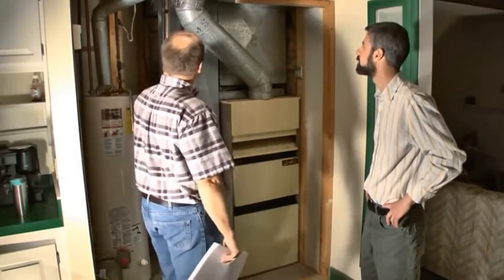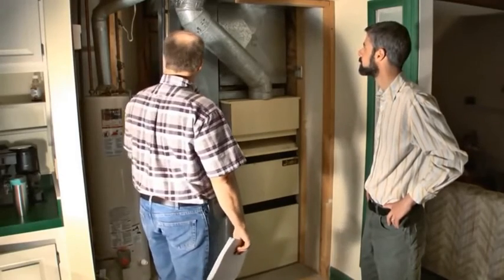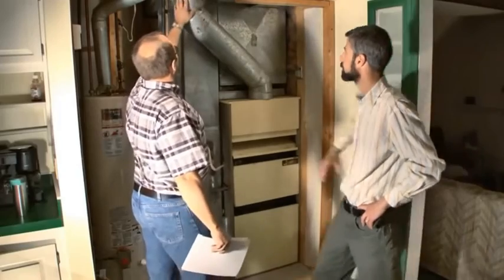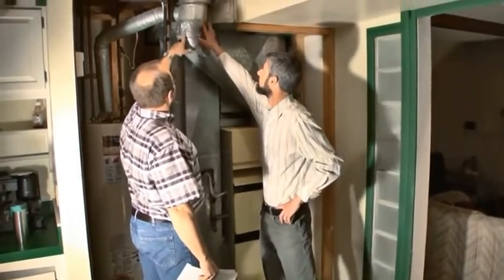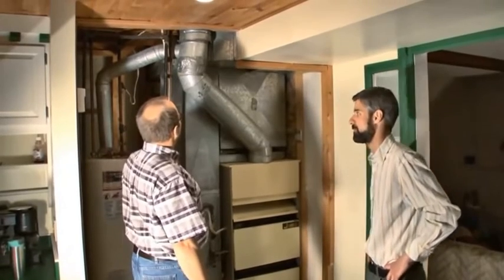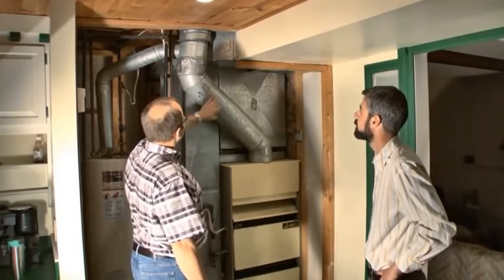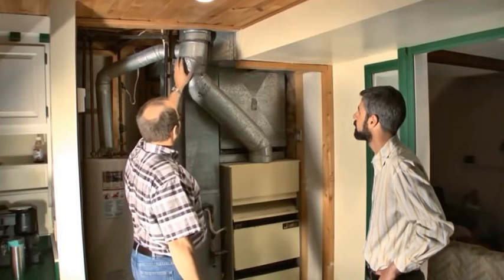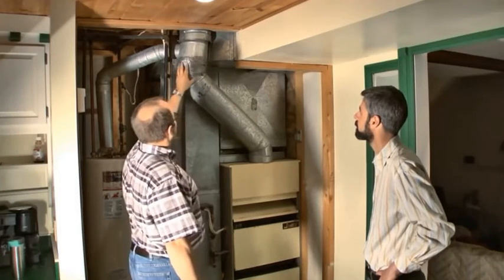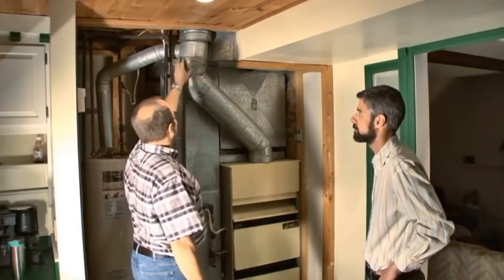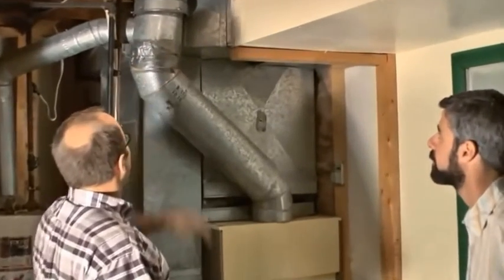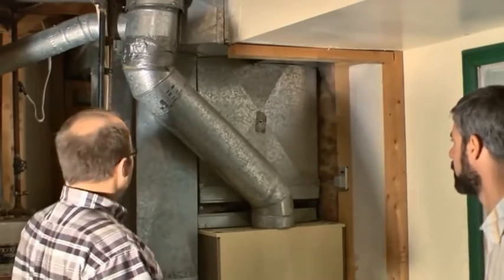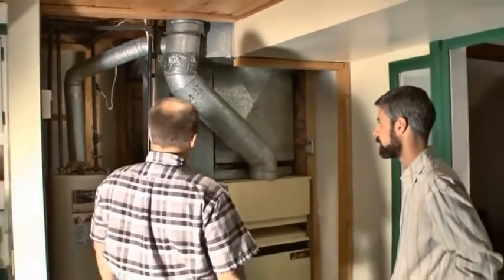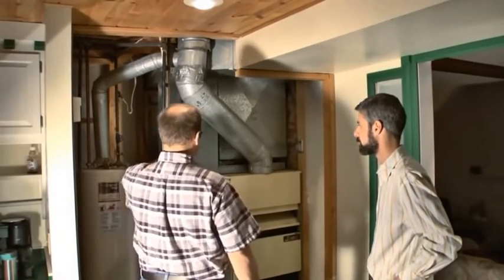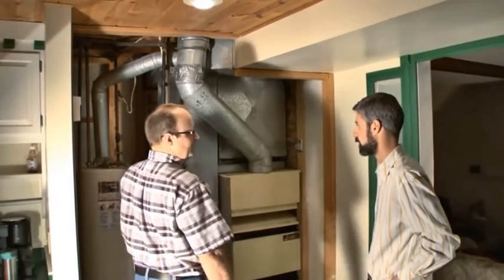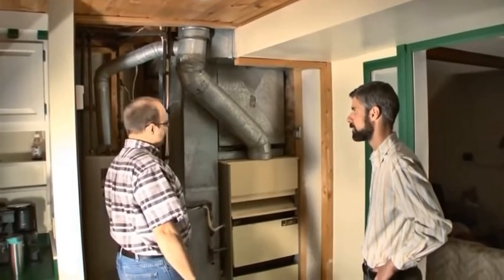Well, when I come into one of these rooms, that's usually what I do: I just take a look at the appliances, look for problems like, for example, this duct tape here. Not good for ductwork, despite the name. No. For one, it's a combustible, and this is the flue pipe, and this has to be 6 inches from any combustible. So this actually could start a fire. So this is not appropriate here. So we'll get that fixed. Yeah. All right. And at first I just generally look around, look for obvious problems before I start all my diagnostics work. But I always look at combustion air. That's the first thing I look for.